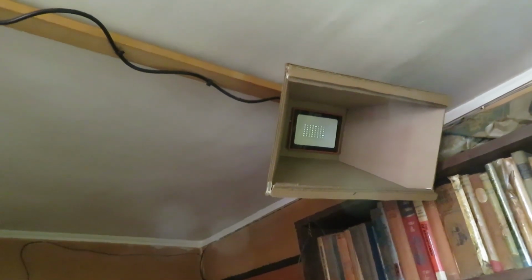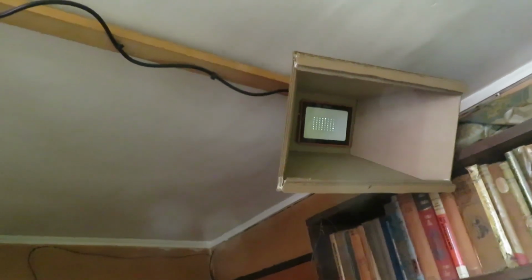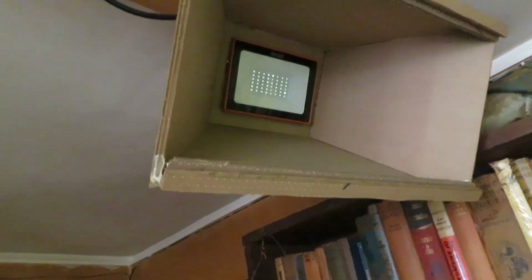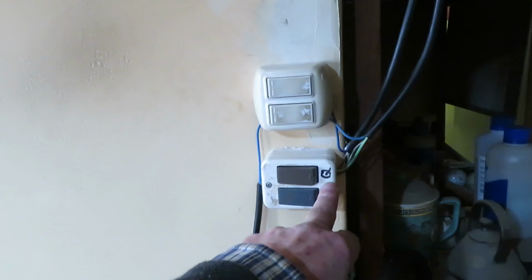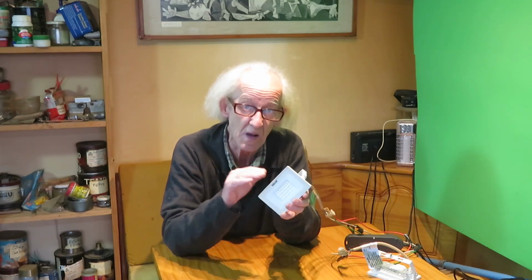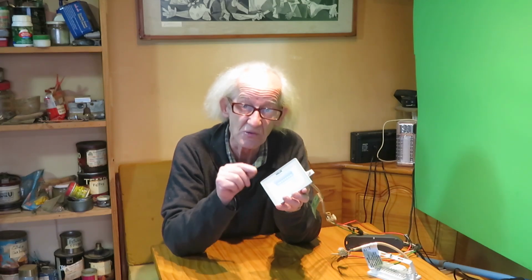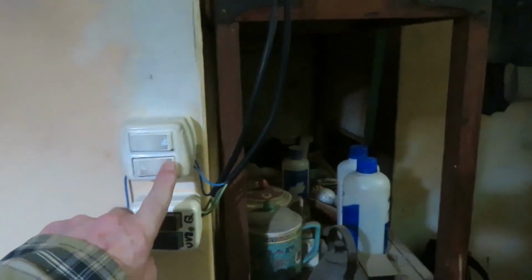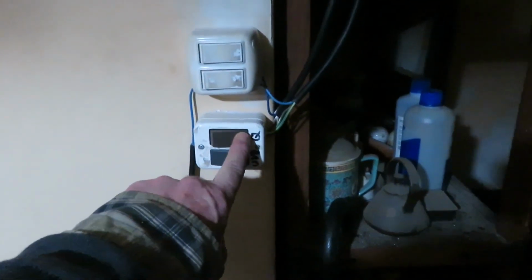But there still is a little glow there. And that little glow comes from the other floodlight. I switch off the other floodlight and now there is no glow. And why is that? Because although each floodlight has its own set of wires, they all come together here in the switch boxes. Now, these floodlights have a metal housing, so we can't leave them without a ground wire while in use. That is, while the power is on. But as soon as the power is off, we can switch the ground wire off.